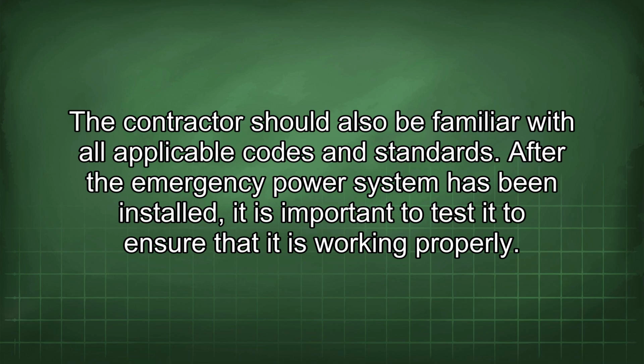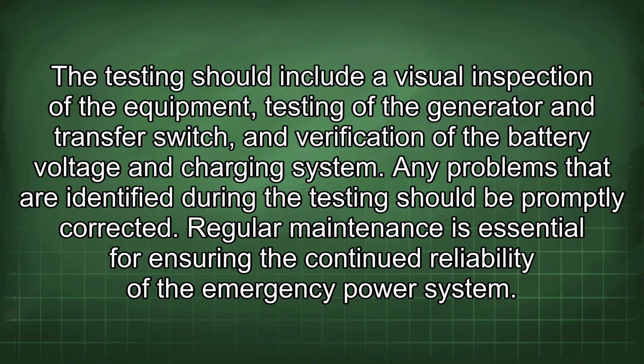After the emergency power system has been installed, it is important to test it to ensure that it is working properly. The testing should include a visual inspection of the equipment, testing of the generator and transfer switch, and verification of the battery voltage and charging system. Any problems that are identified during the testing should be promptly corrected.